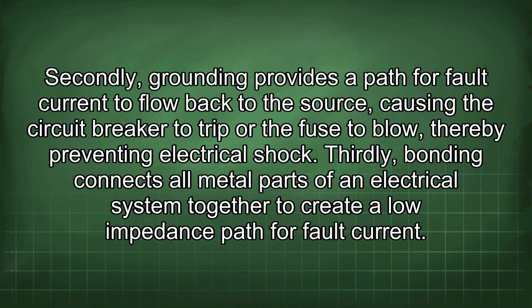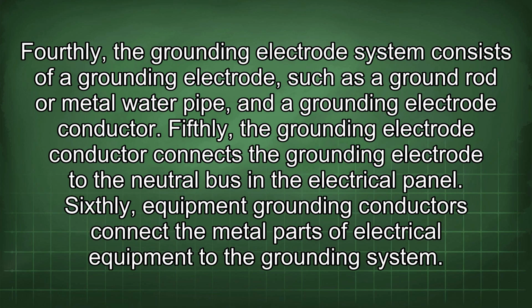Thirdly, bonding connects all metal parts of an electrical system together to create a low impedance path for fault current. Fourthly, the grounding electrode system consists of a grounding electrode, such as a ground rod or metal water pipe, and a grounding electrode conductor. Fifthly, the grounding electrode conductor connects the grounding electrode to the neutral bus in the electrical panel. Sixthly, equipment grounding conductors connect the metal parts of electrical equipment to the grounding system.